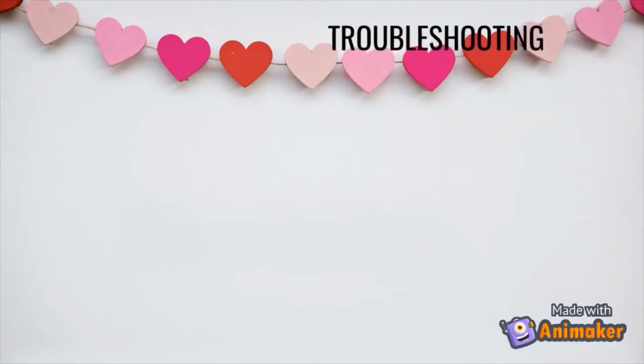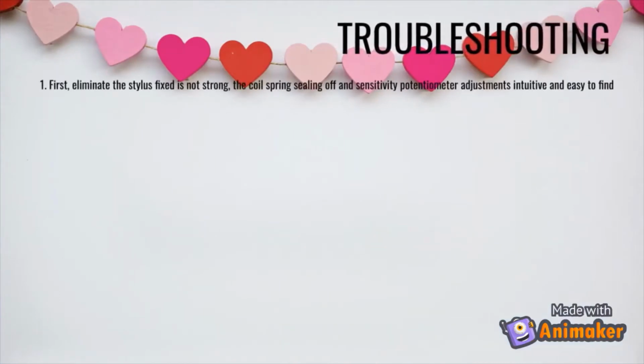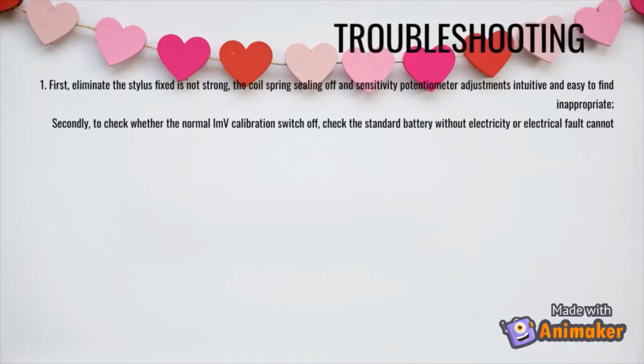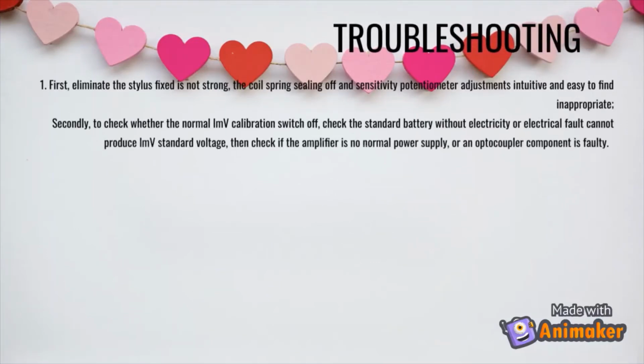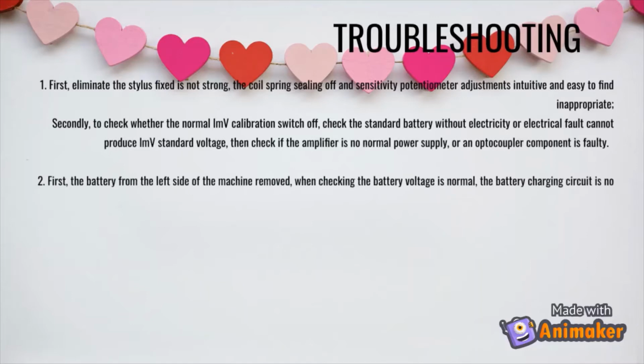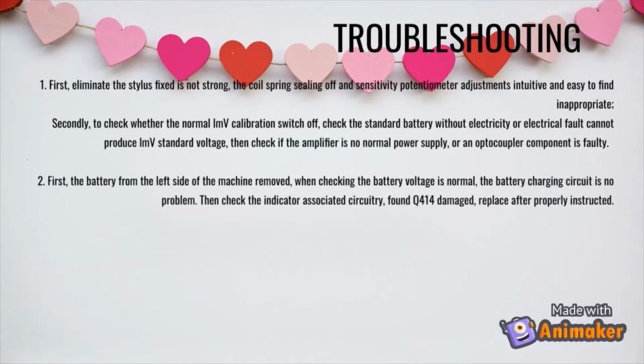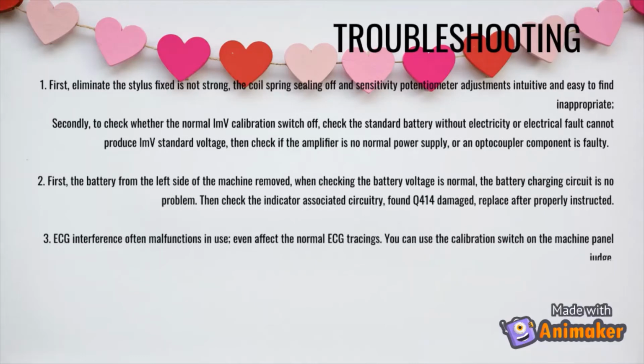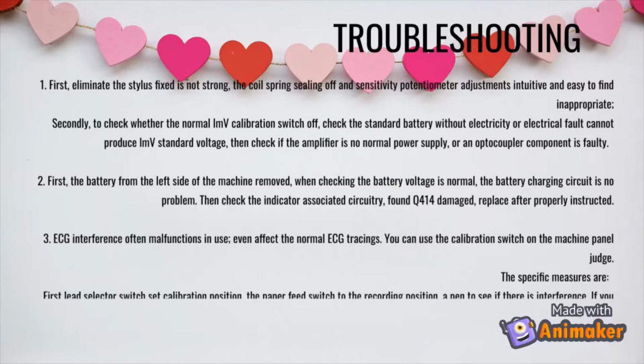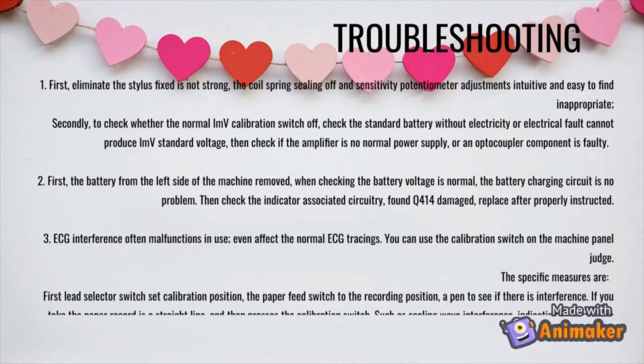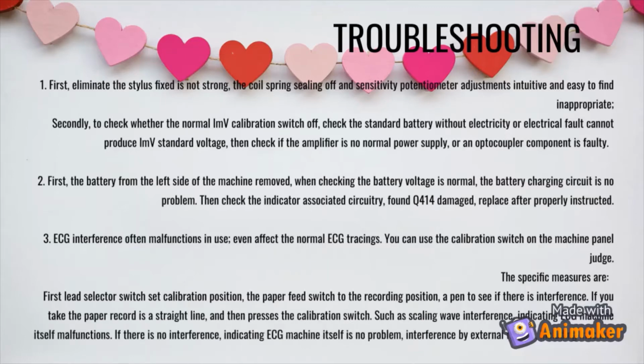Troubleshooting: first, eliminate that the stylus fixed is not strong. The coil spring, sealing off and sensitivity potentiometer adjustment are easy to find inappropriate. Secondly, check whether the normal 1mV calibration switch is off. Check the standard battery without electricity, or an electrical fault that cannot produce the 1mV standard voltage. Then check if the amplifier has no normal power supply or an optocoupler component is faulty.